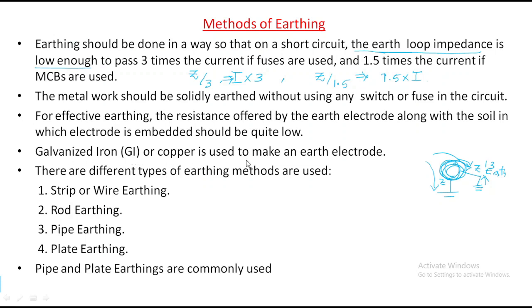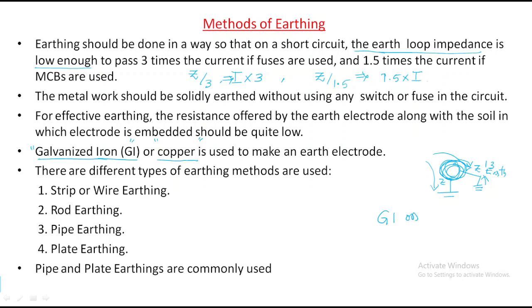Galvanized iron (GI) or copper is used to make an earth electrode. So, in order to make the earth electrode, which type of material are we using? One is galvanized iron and the other is copper. These are the two materials generally used for earthing. This is very important. Why are we using them? These are high conducting materials. Whenever high conducting properties are there, it will automatically be grounded, to make the earth electrode.